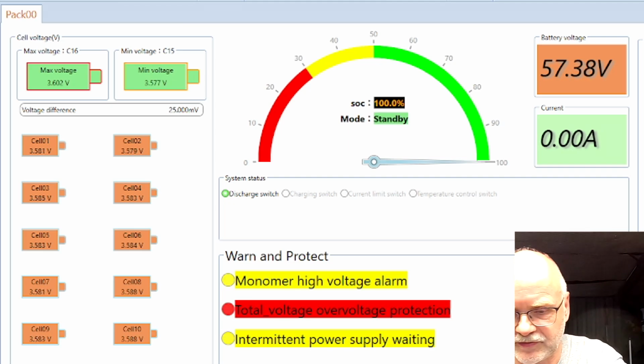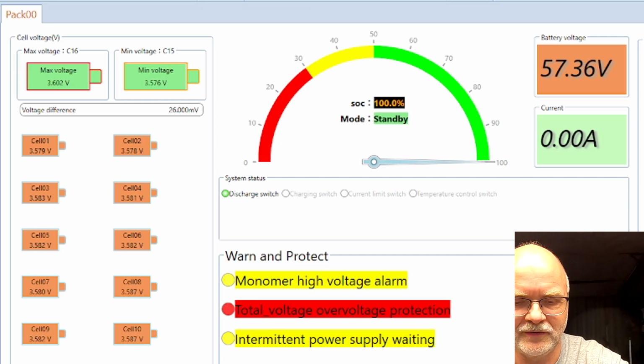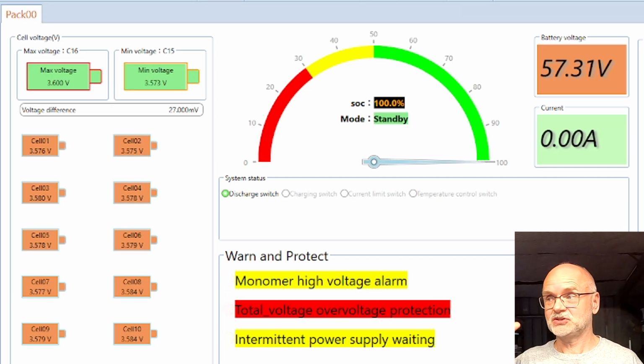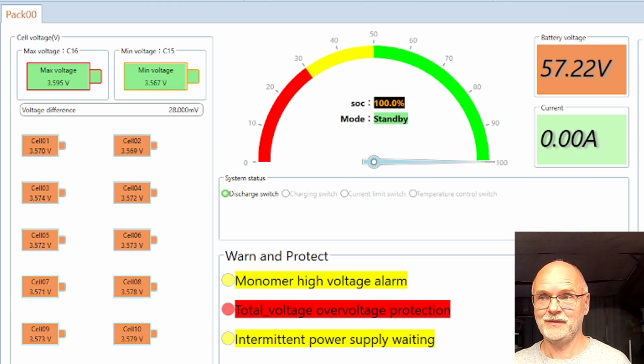I'm going to disconnect the active balancer because we don't want it running during our discharge test. Now we can't further charge the battery because the settings have decided 57 volts is enough for the whole pack. Something's not right, nobody charges that high usually, so I'd better turn off the charger. Totally fine, it's a safety feature of the BMS, of any BMS.